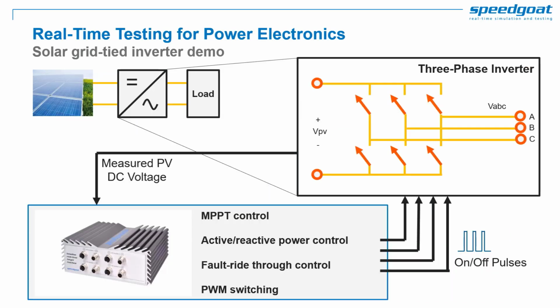Once we design our controller for the solar inverter, we'll use rapid control prototyping to test it with the actual hardware. It is easy to implement controllers with different levels of fidelity on a Speedgoat target machine. For example, MPPT controls will run at millisecond range, while the PWM switching will have a resolution of nanoseconds.